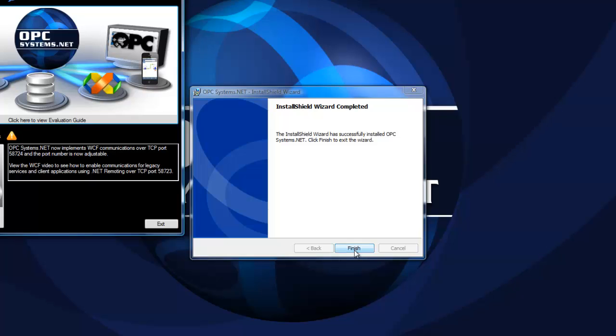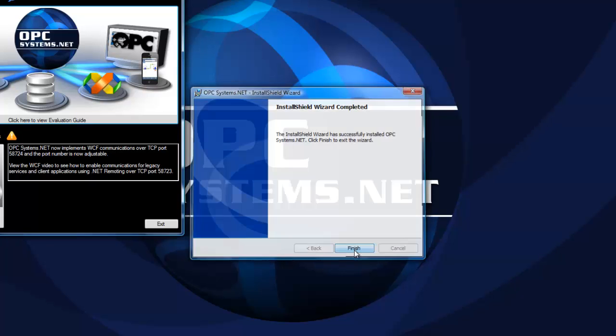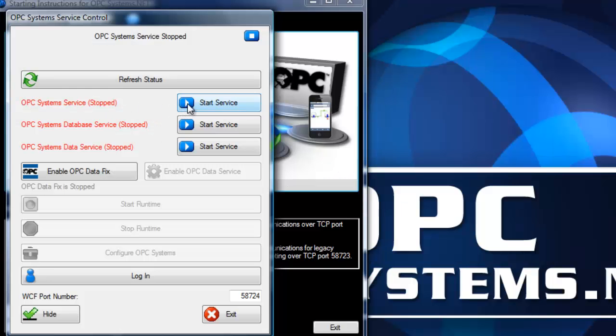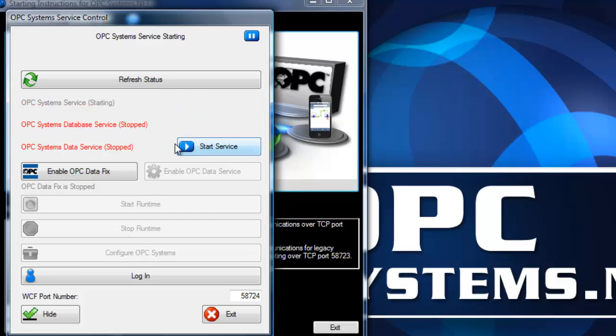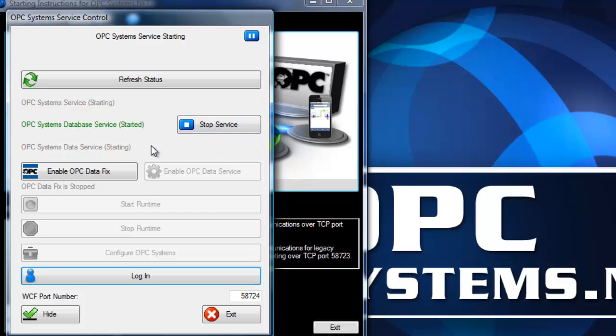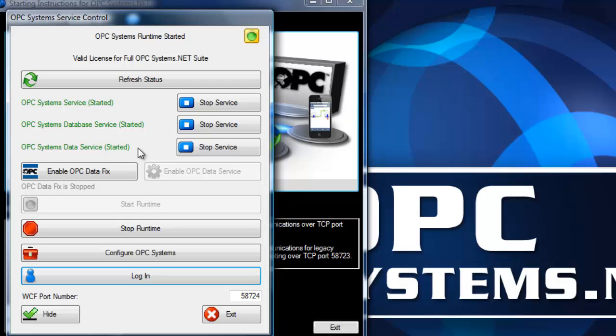Once the setup completes, you'll select the Finish button and then the Service Control Manager will appear where you can start the three OPC system services. If you're connecting to OPC servers that run as a desktop application, you may want to enable the OPC data fix. If you're connecting to OPC servers that run as a Windows service like Kepware, you can use the default to run the OPC Systems data service under the system account.